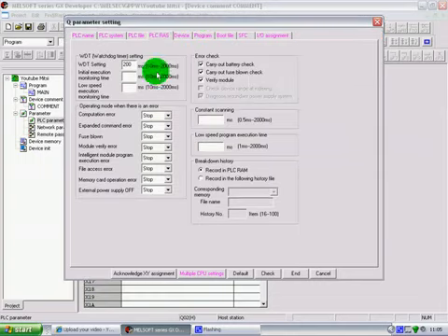If you go to PLC RAS, you will notice that you have operating mode when there is an error. So these are a list of items that can cause the system to go into stop. However, if you don't want them to go into stop, if you want them to continue, for example, let's say the fuse blown, you can select that system to continue without it going into stop mode.